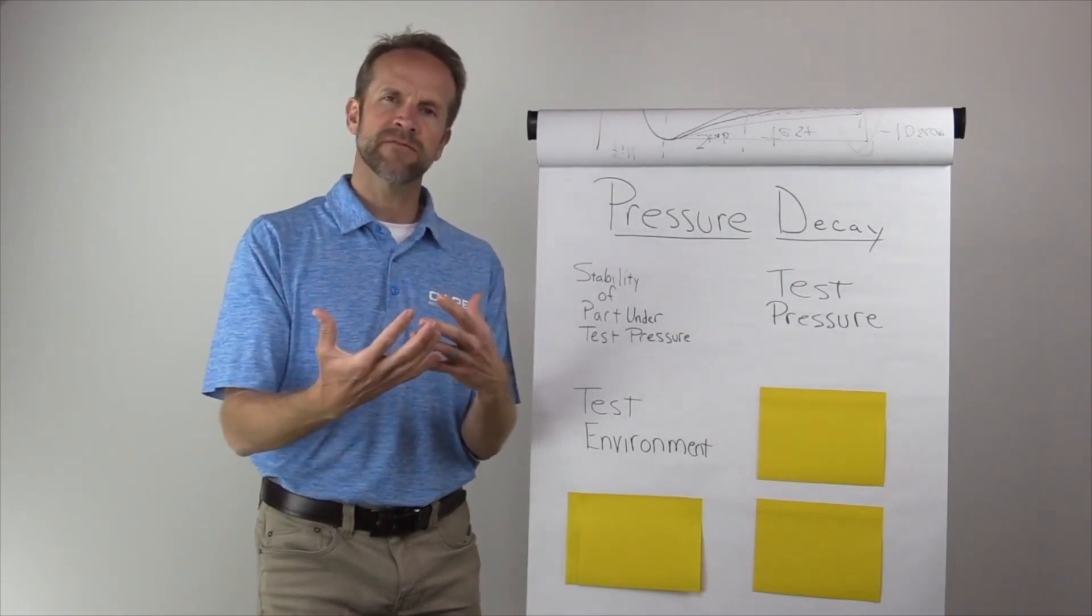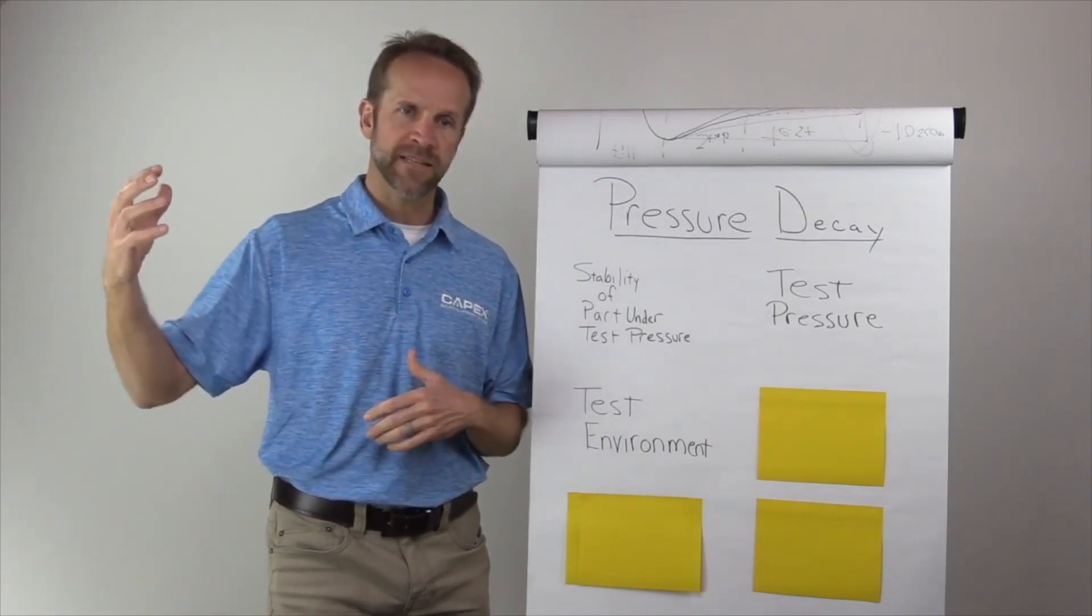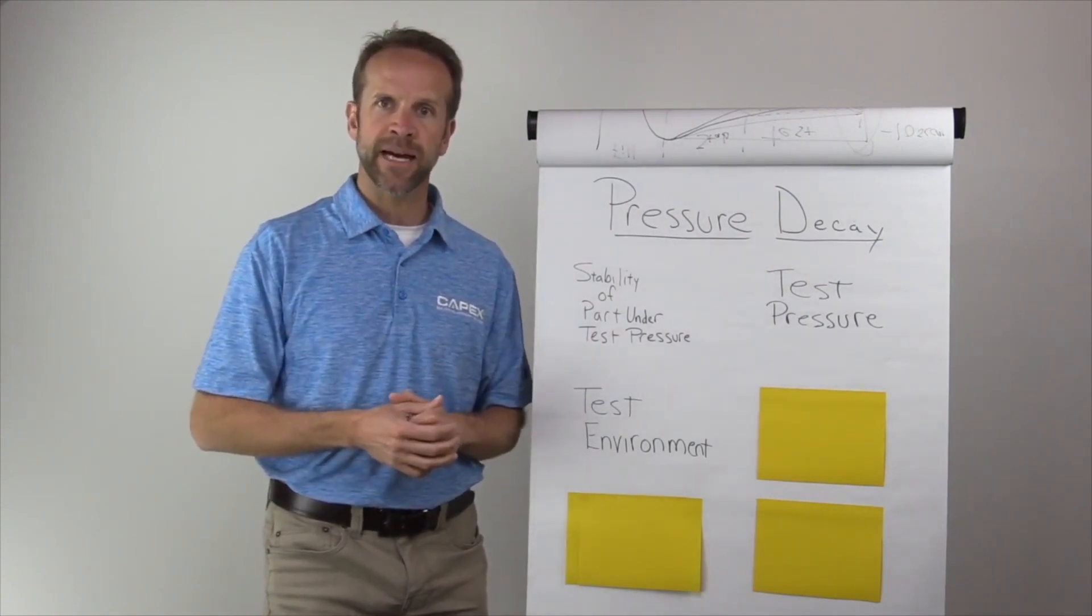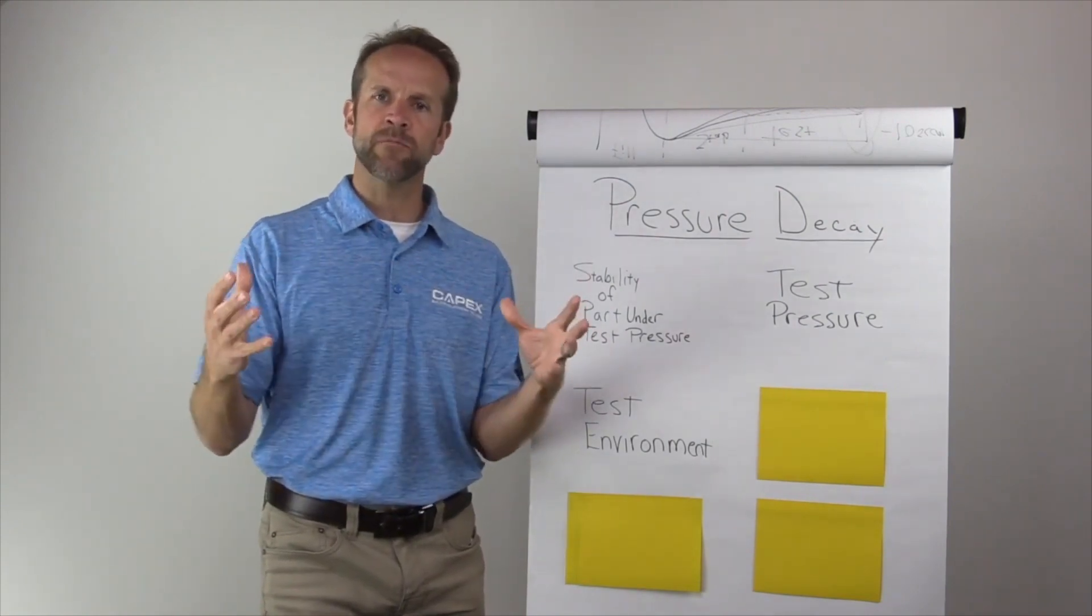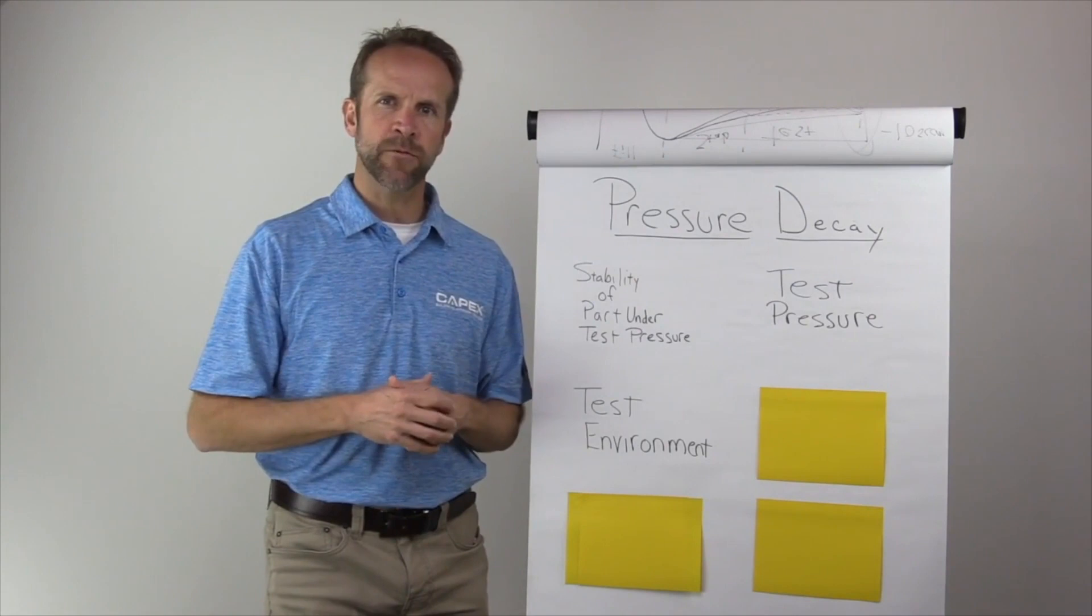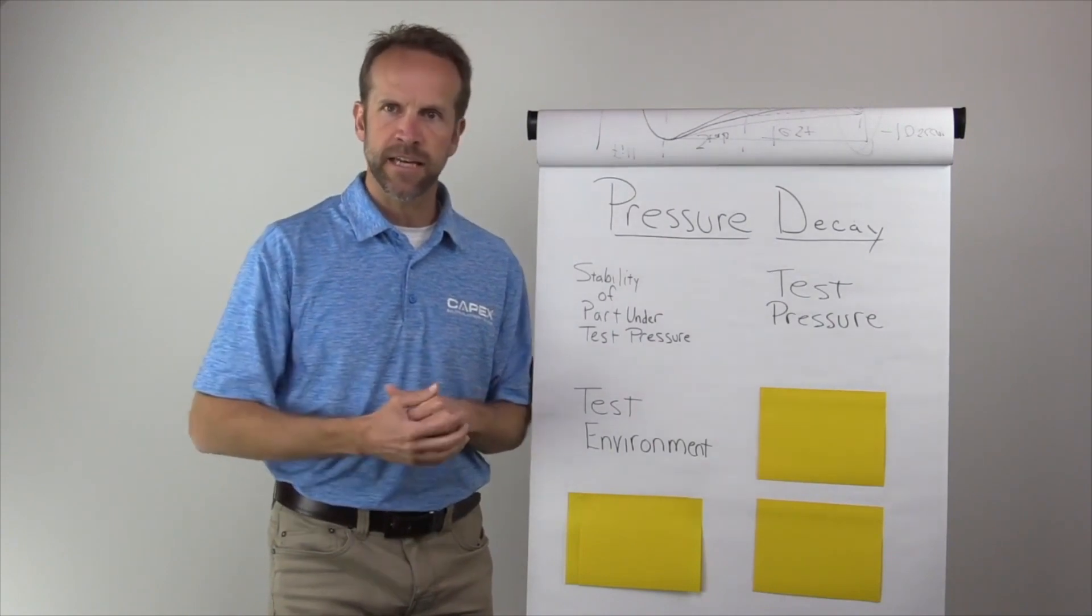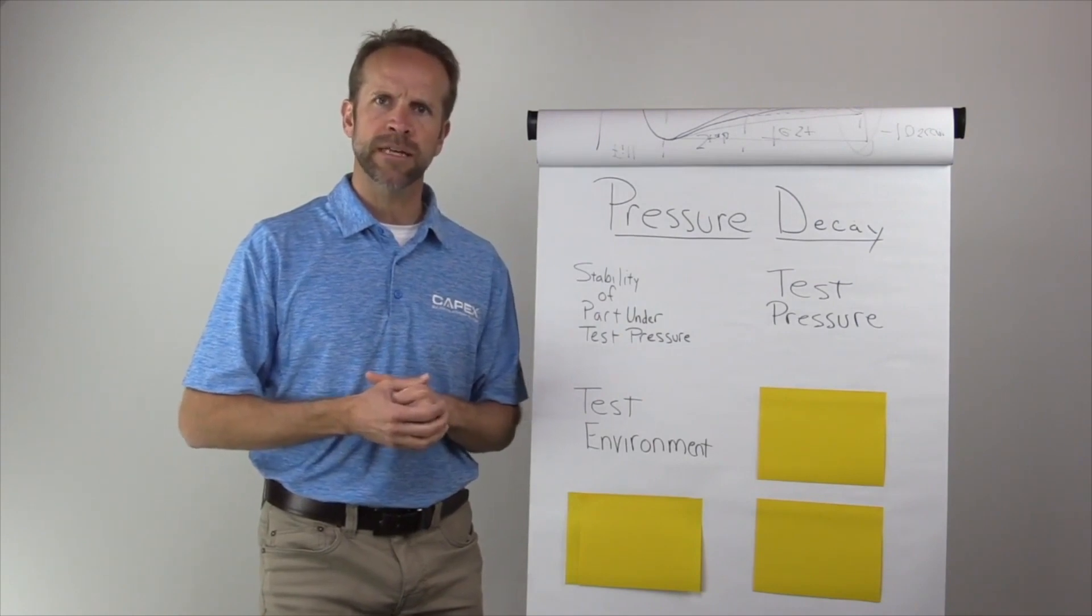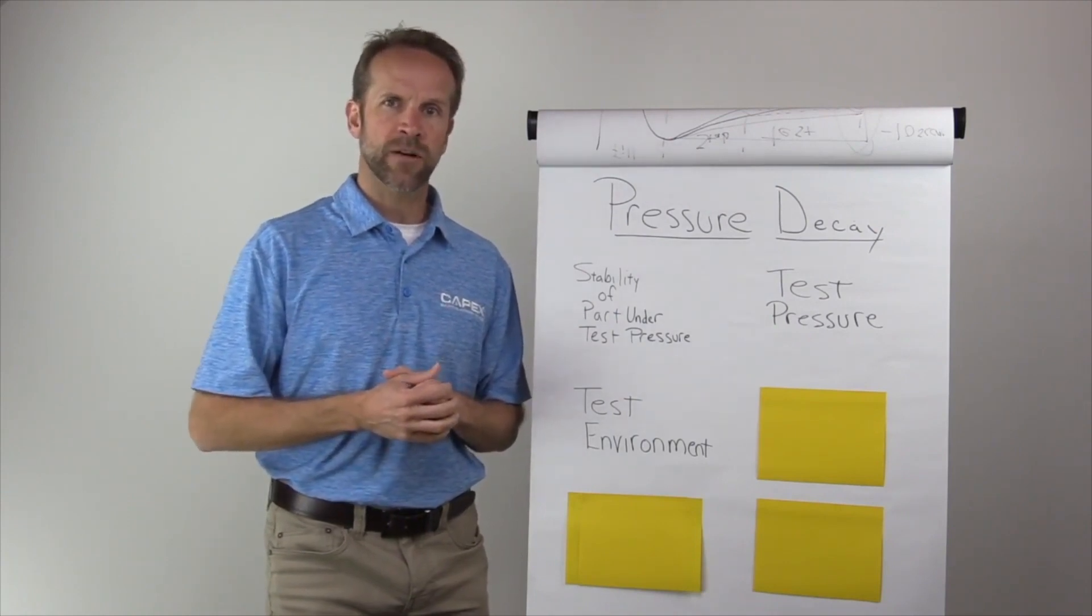So the environment, the test environment is extremely important. If you have a fan, if the operator needs a fan blowing on them, that fan is going to blow the air onto the part that you're testing. And depending on the leak rate, it's definitely going to have an impact on the repeatability and stability of your test application. So the environment in which you are performing a pressure decay test is extremely important, especially for those low leak rate applications. Now, when I say low leak rate, I'm talking things 10 SCCM, 5 SCCM, 3 SCCM, 1 SCCM.